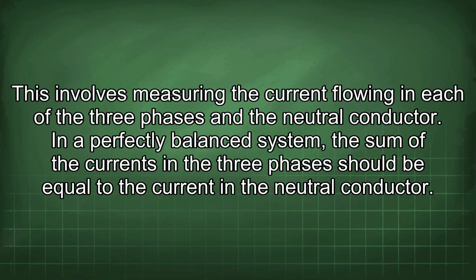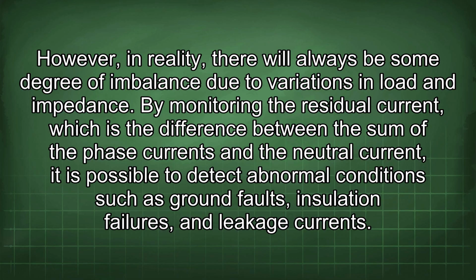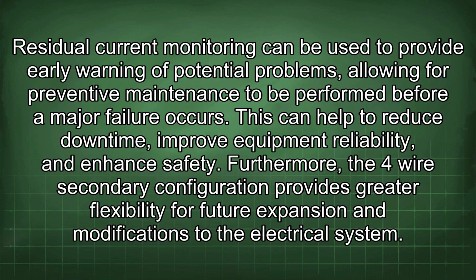monitoring. This involves measuring the current flowing in each of the 3 phases and the neutral conductor. In a perfectly balanced system, the sum of the currents in the 3 phases should be equal to the current in the neutral conductor. However, in reality, there will always be some degree of imbalance due to variations in load and impedance. By monitoring the residual current, which is the difference between the sum of the phase currents and the neutral current, it is possible to detect abnormal conditions such as ground faults, insulation failures, and leakage currents. Residual current monitoring can be used to provide early warning of potential problems, allowing for preventive maintenance to be performed before a major failure occurs. This can help to reduce downtime, improve equipment reliability, and enhance safety.